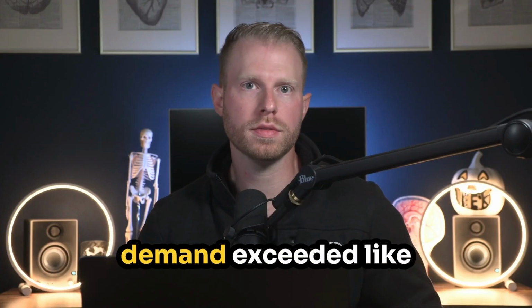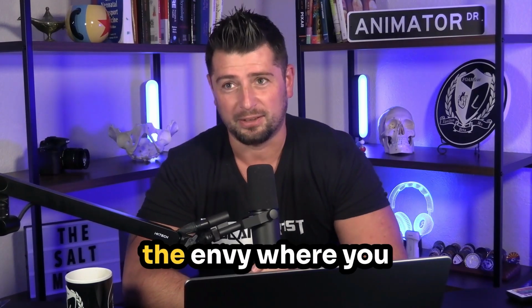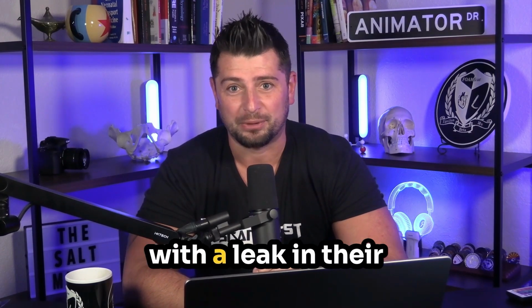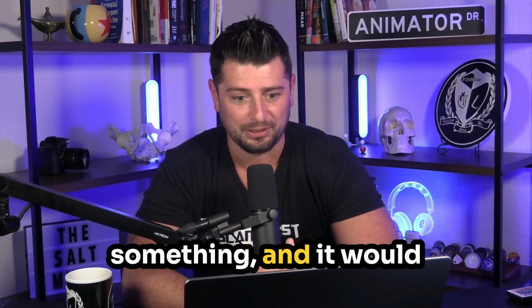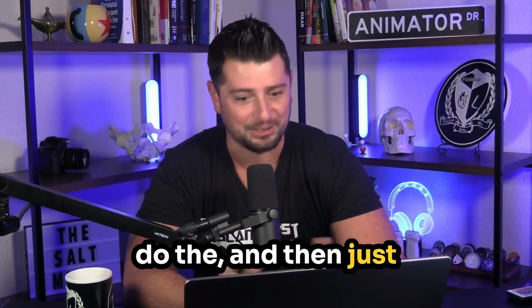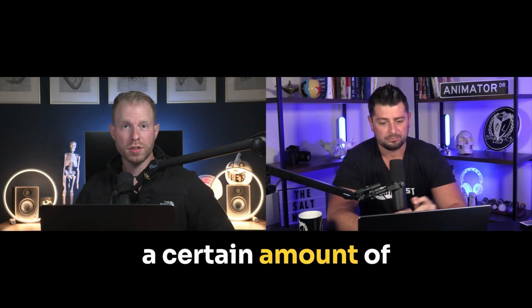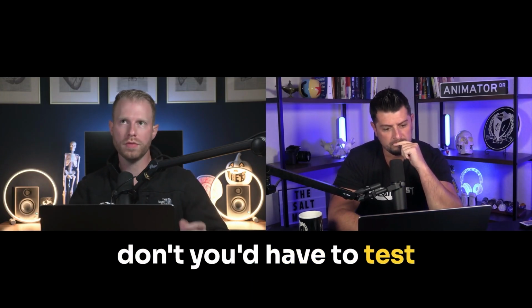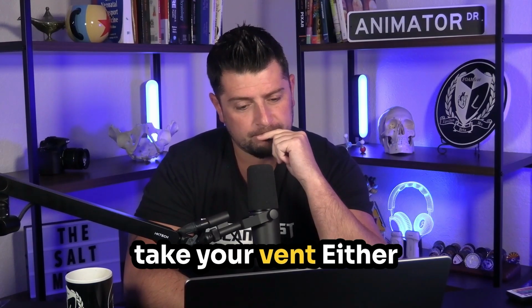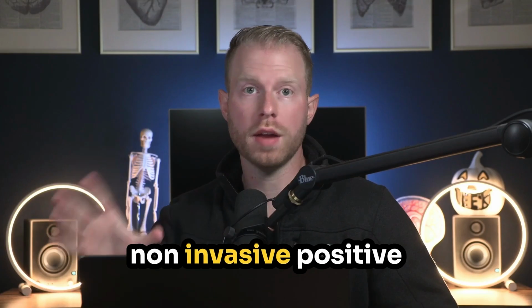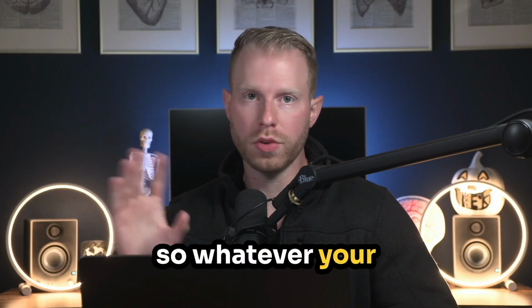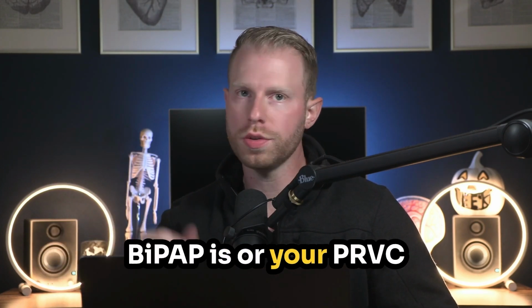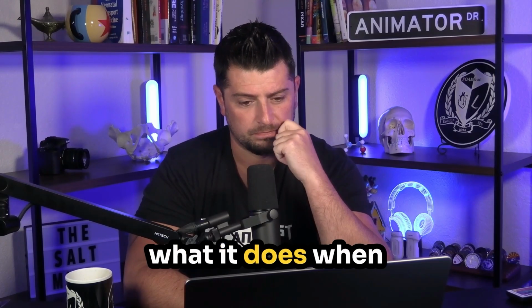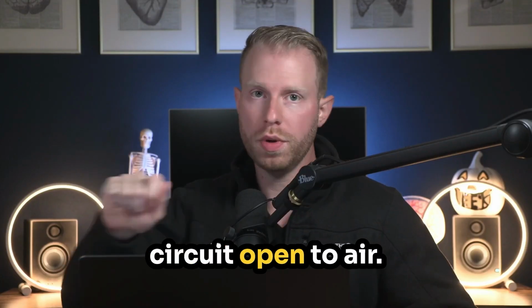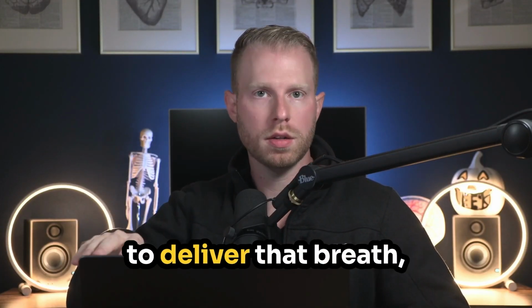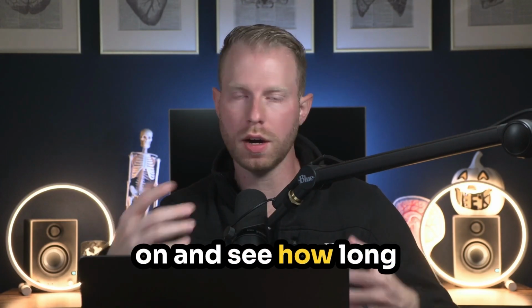So I haven't seen blower demand exceeded like we used to see on the Envy, where you would have somebody with a leak in their BiPAP mask or something, and it would do the whoosh, whoosh, whoosh, and then just stop. But it cuts off after a certain amount of time, so I don't know how many vents do or don't; you'd have to test it, and it's real easy. Take your vent and put it on your non-invasive positive pressure setting, whatever your BiPAP is, or your PRVC mode, and see what it does when you just have the circuit open to air. See if it'll just keep trying to deliver that breath, and then put a test lung on and see how long it takes to calibrate.